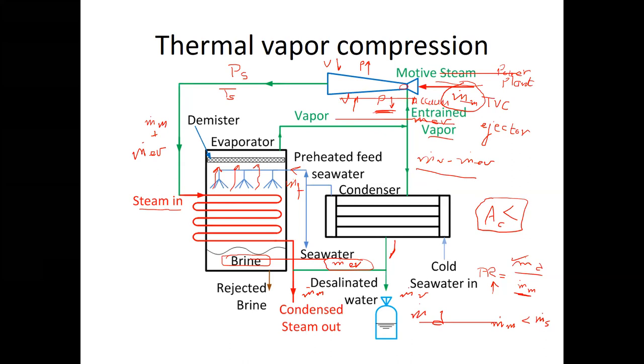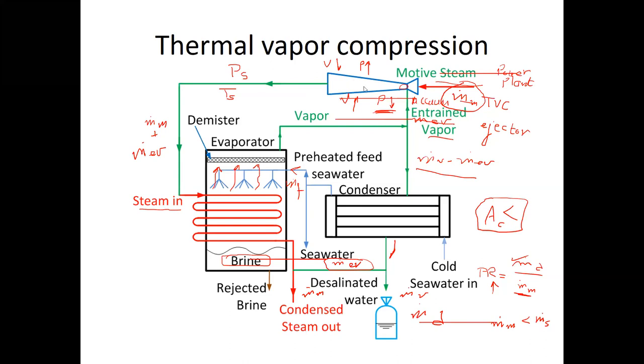The system now has three components: the condenser seen earlier, the evaporator evaluated earlier, and the new unit — the thermal vapor compressor, TVC, or ejector. If you pass by any desalination system — in Khubar, Al-Aziziyya, Jubail, or Marafiq — you will always see on top of the desalination unit something several meters long with the shape of a convergent-divergent nozzle or venturi. This is the TVC, and it has become an essential part of desalination systems with several utilizations.